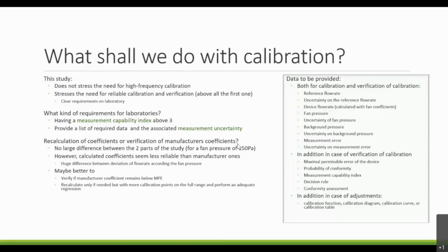So if new coefficients shall be recalculated, they shall be done with more than 3 points and with a more appropriate regression than just a linear regression. And so it may be better to just verify if manufacturer coefficients remain below the maximum permissible error, and calculate only if needed, but with more calibration points on a full range of pressure and perform an adequate regression.